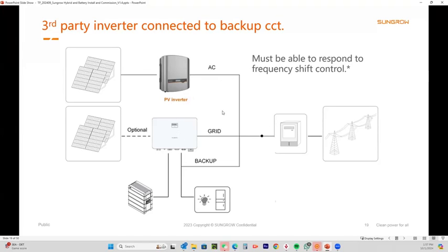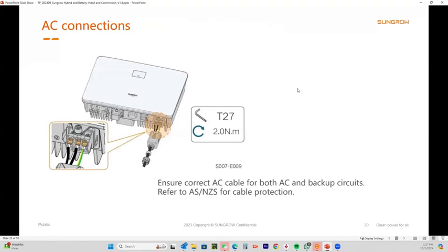There's a setting where you actually enable that feature. So in this case, you can AC couple and put the third party system onto the backup circuits, and that will keep going every day. Obviously when the sun goes down, this inverter shuts down as normal, but when the sun comes back up, as long as this is in operation, pumping out grid voltage and frequency, the inverter will start up. So if you want to do that and you're not quite sure, give us a hoy and we'll give you the information.